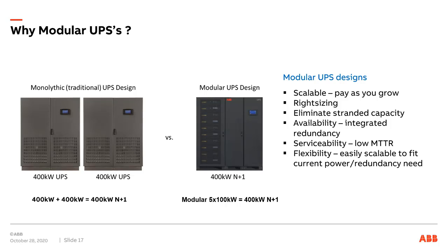What would make that attractive to the customer, or the example I just gave, is that the customer can start by installing the frame and putting 1 module in there, or 2. 2 modules will give him up to 100 kW N+1 redundancy, and then as they add more load, they can add more power modules up to a maximum of 5, but they get the same redundancy in practically half of the footprint.